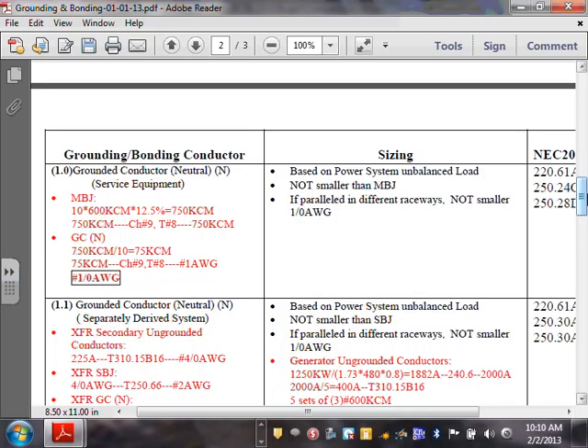Now I do a lot of calculation for commercial, residential, and industrial buildings, guys. But because I'm an engineer, I have a lot of Excel sheets. If anybody wants some, I'll shoot it your way too. So, it's really hard to predict the neutral at that level, at the level of 4,000 amp. By the time you reach the level of 4,000 amp switchgear, guys, remember all your lighting system has been balanced. All air handling units, all your mechanical equipment, HVAC equipment, heating, cooling, and ventilation equipment, all of them are three-phase, do contribute big fat zero to your neutral, right? So by the time you reach a 4,000 amp switchgear, the neutral size is substantially small, substantially.